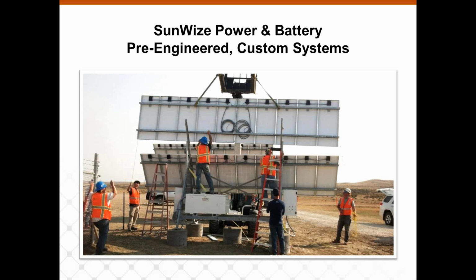And I saw the question about monitoring through the controller. Again, Morningstar's maximum power point controllers, the larger ones, offer access points for monitoring the load and input through the array, and everything to do with the health of the power system. Morningstar has a very excellent algorithm for that, developed over a number of years, which allows them to optimize the power charge as a result of that algorithm.